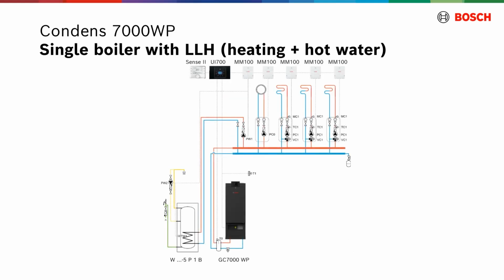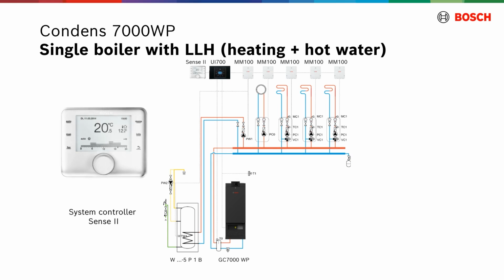In this heating system, to control heating and cylinder circuits, the EMS-based system controller Sense2 is required. For every heating circuit, one function module MM100 should be assigned and the coding switch addressed from 1 to 4. Outdoor temperature sensors T1 and temperature sensor T0 at the low-loss header are connected to the boiler.